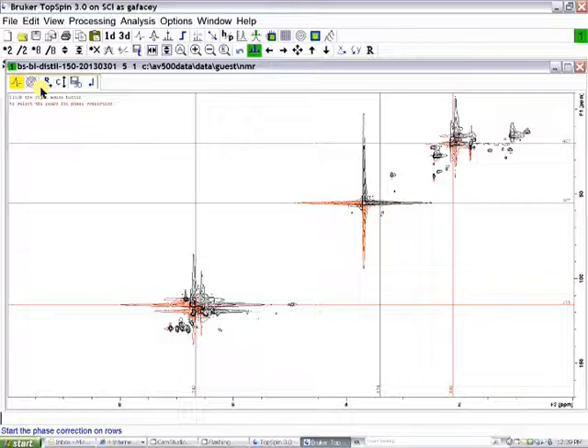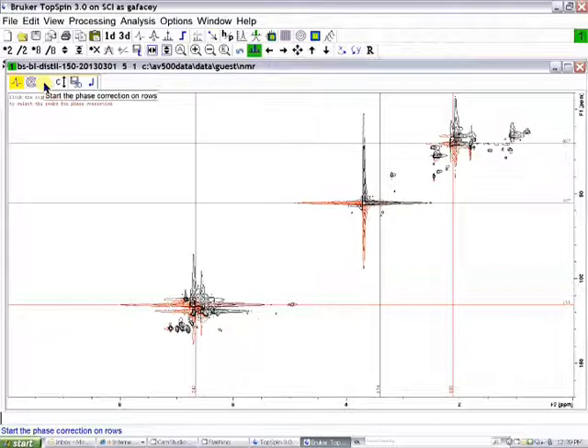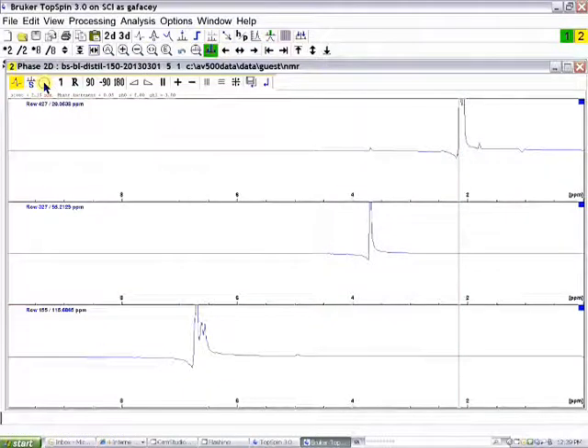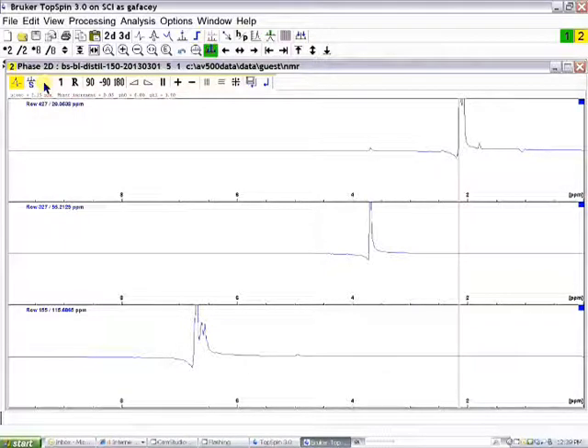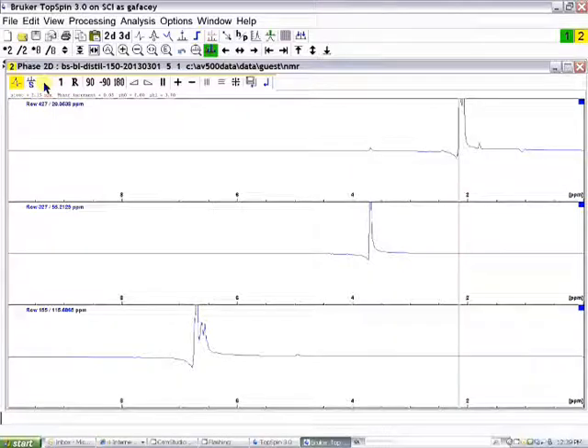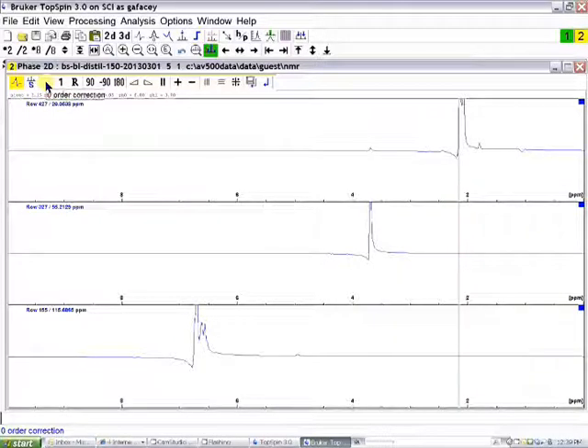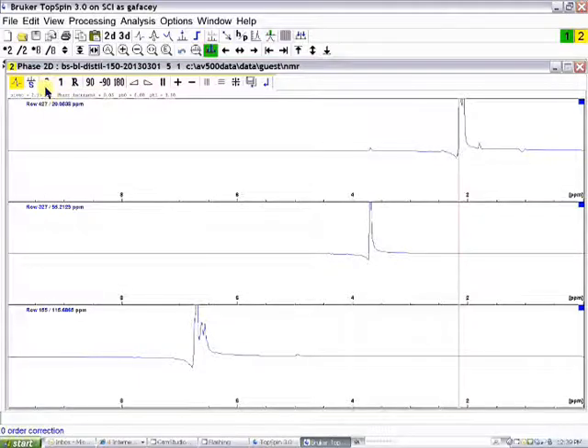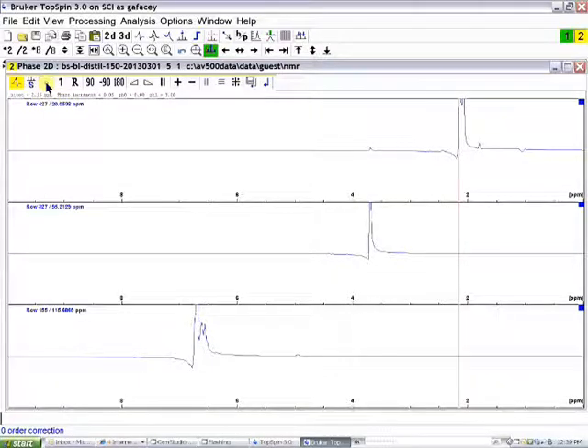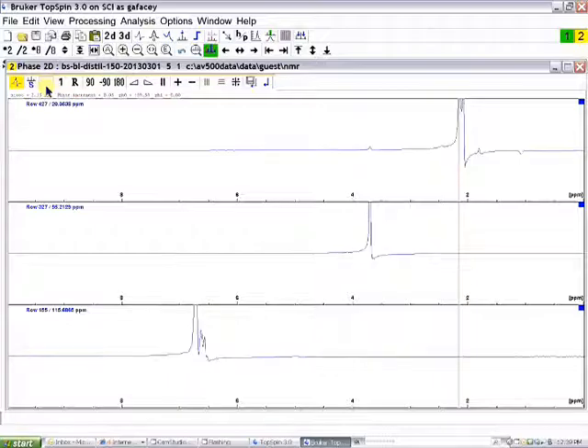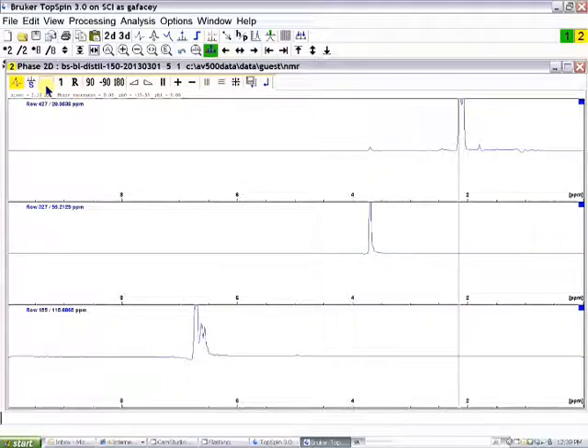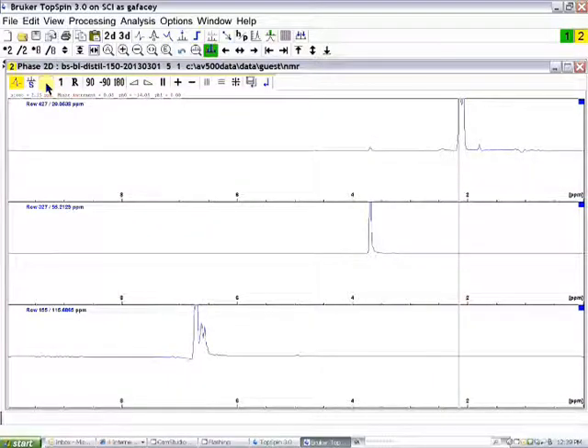And then we click on the R icon within the phasing routine, which will show us the three rows that we've selected. You can see that on the top spectrum there's a red vertical line on the largest peak in the spectrum. If I want to phase this to zero order, I put the mouse on the zero order phase correction, hold the left-hand mouse button, drag the mouse up and down until the peak in the top spectrum is in phase.